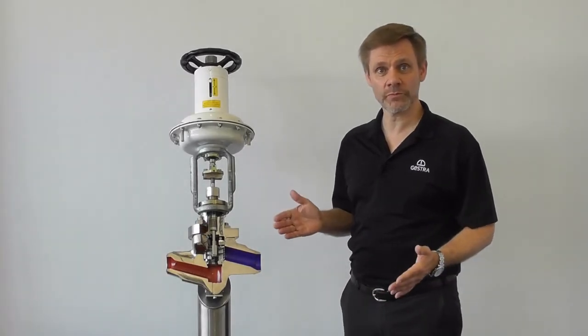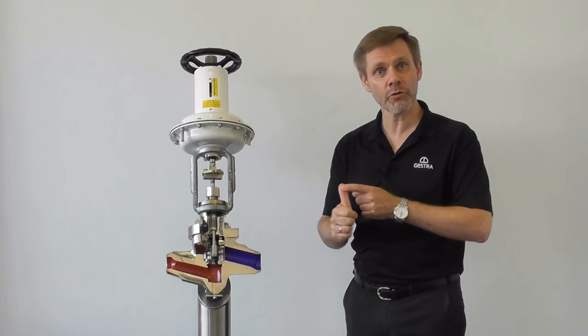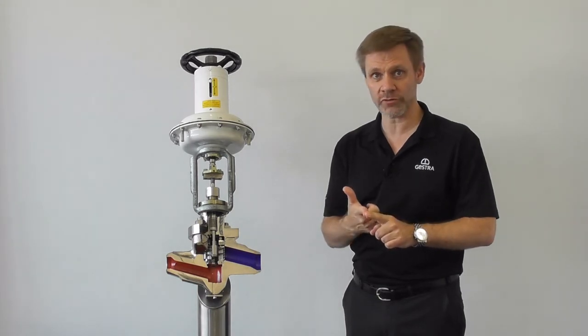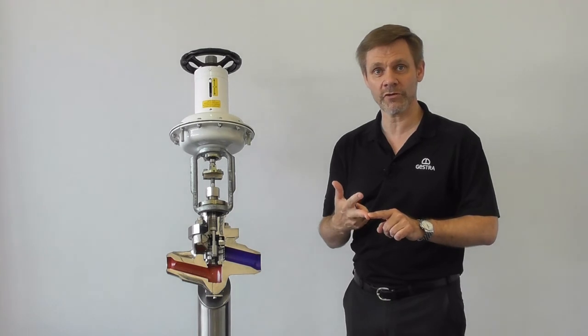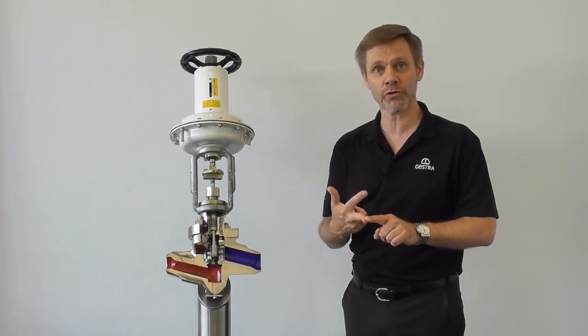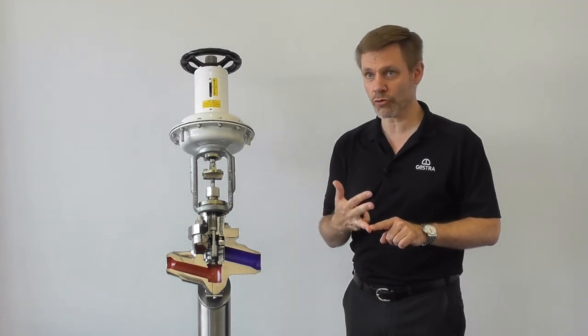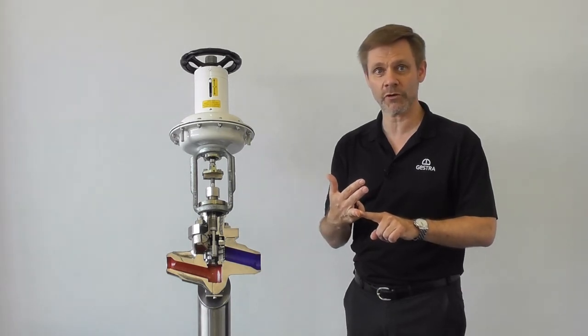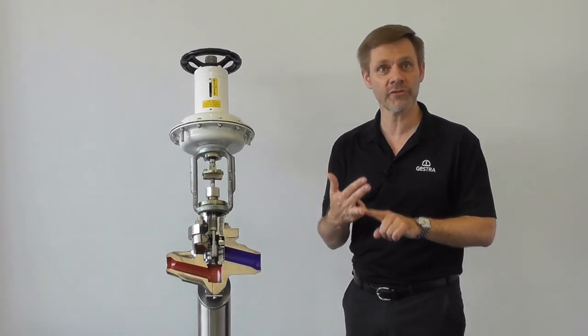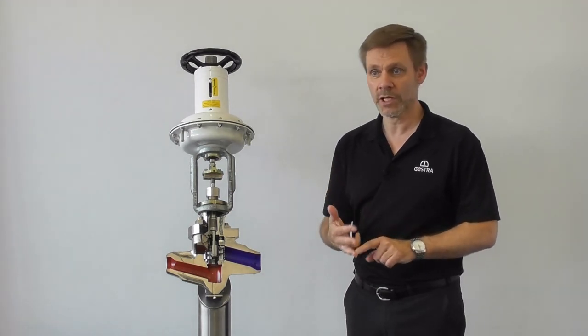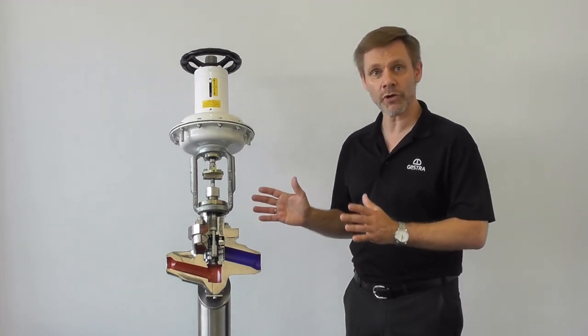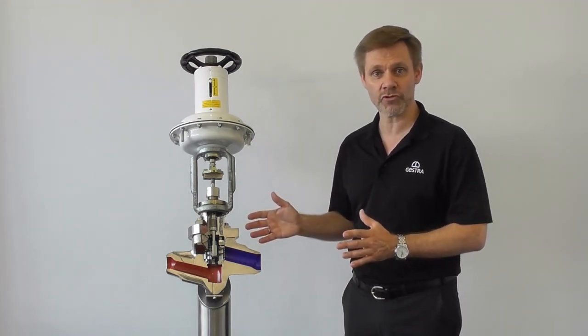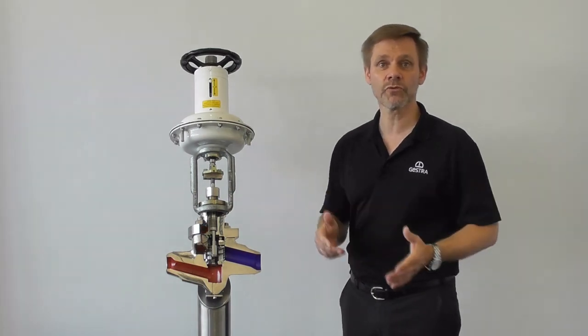What are the benefits of this valve for you? First you will have a perfect tight shut off with the control valve. This guarantees for you no energy losses. You won't have any thermal shock damages in steam coolers if you are using this valve as a spray water control valve. You have a very good control performance over a long time by avoiding washing out of the seat surfaces and of the trim itself. That means that you keep a stable control characteristic. We have a very reliable trim design for extremely high differential pressures. That means the valve can stay for a long time in operation without maintenance.